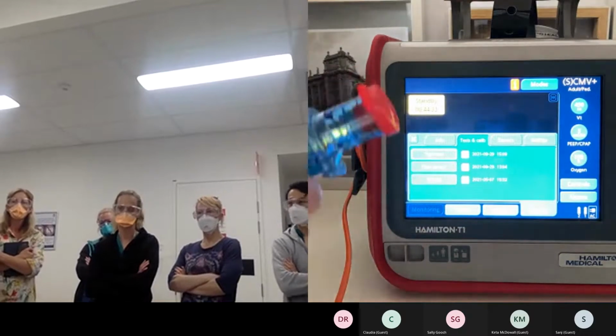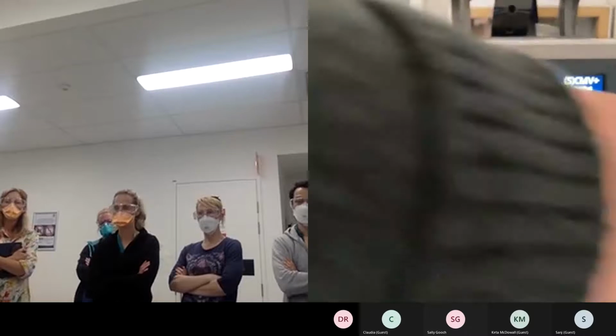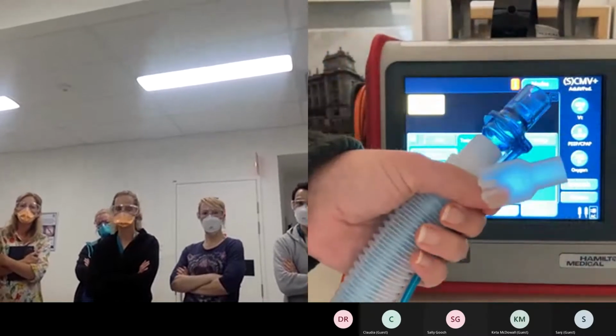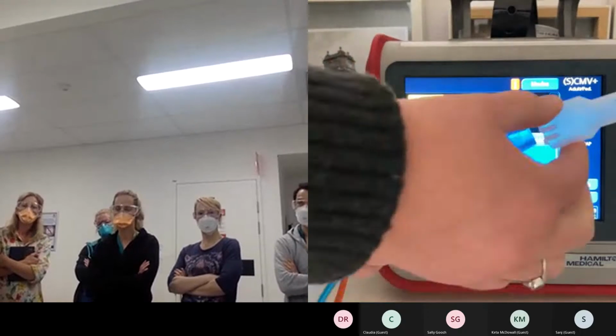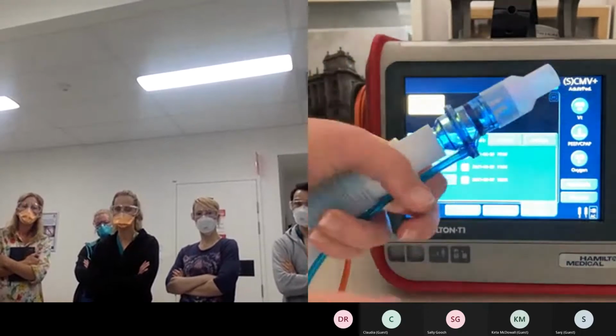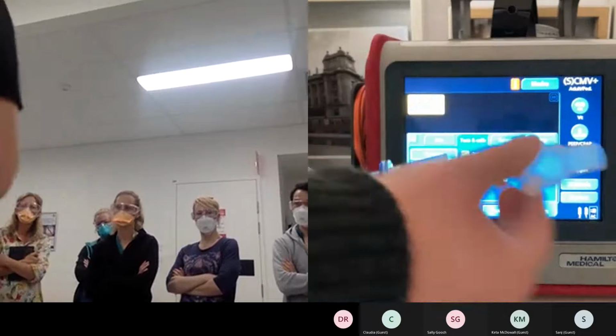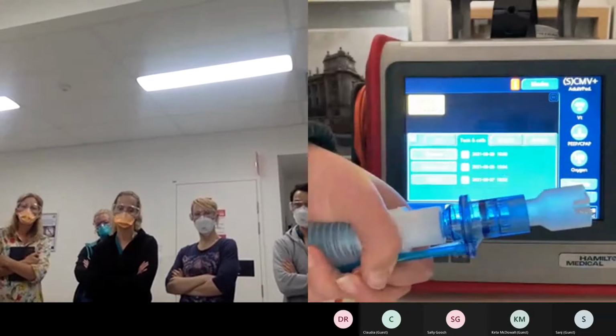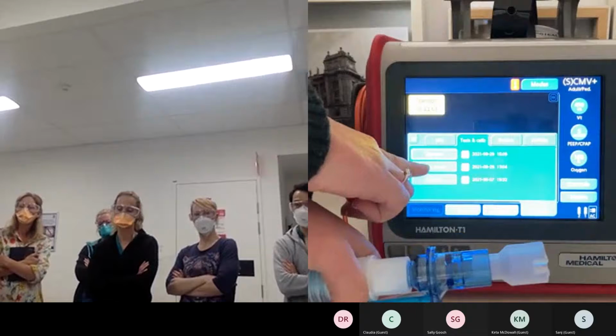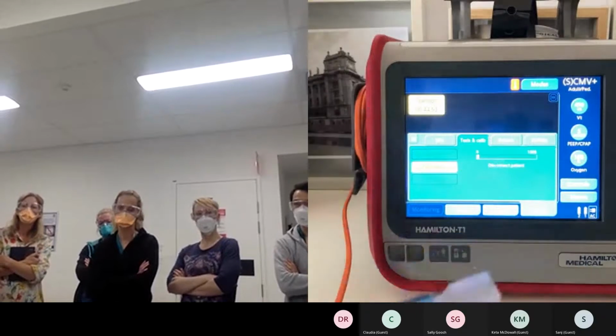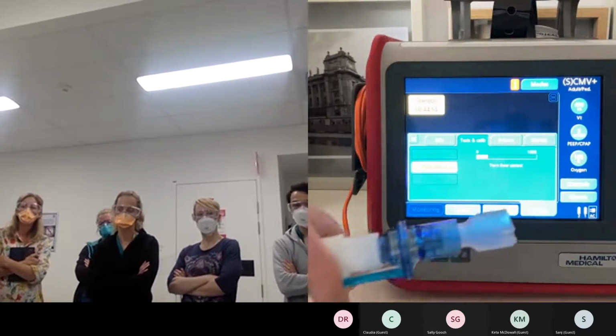Then you've got your flow sensor test. So this is the calibration of the flow sensor, and you need this little connector. Sorry, that's a bit close. You need this little connector, and it fits into the end, and it comes in every pack. Okay, and it can fit both ways, so it doesn't matter which way you pop it on. Then when you touch on flow sensor, it's going to tell you to disconnect patient. So we've already done that.